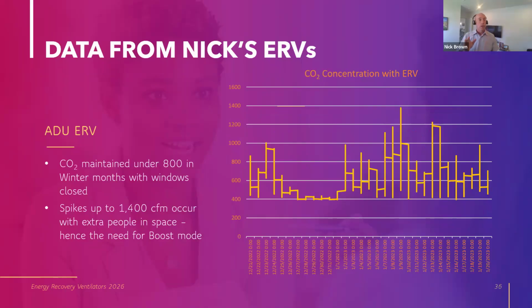I also spied on my tenants' CO2 level. I put an air monitor in their space. And here's what it showed. It showed that even with that ERV running, periodically they spiked up to above 1,000 parts per million of CO2. 1,400 one day. They must have had a bunch of people over. So it really shows the need for the ability to boost mode your ventilation system and provide extra ventilation when a lot of people come over.